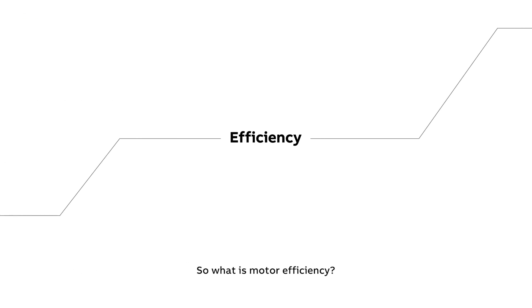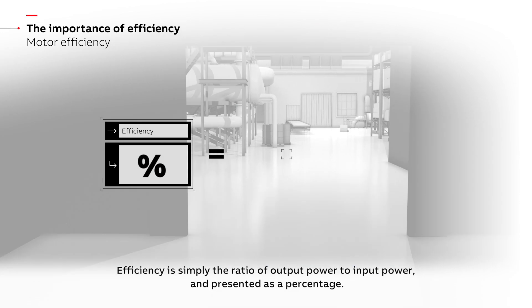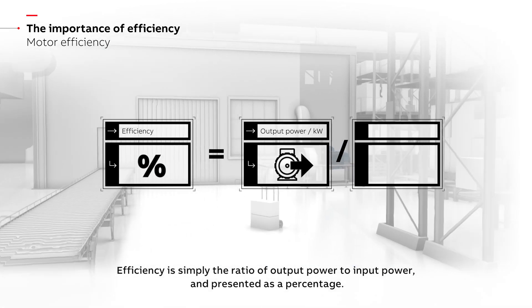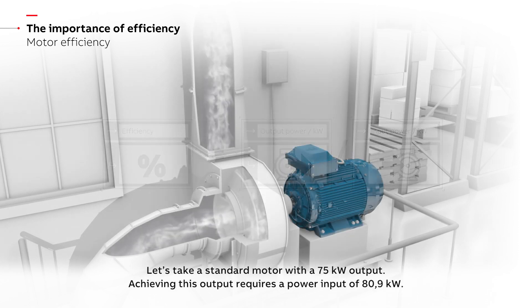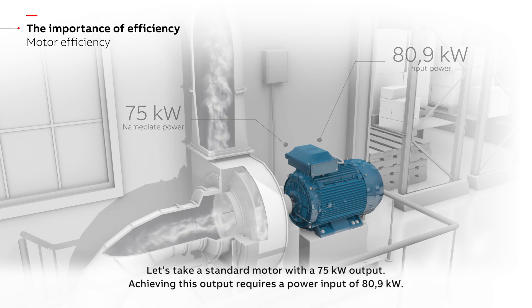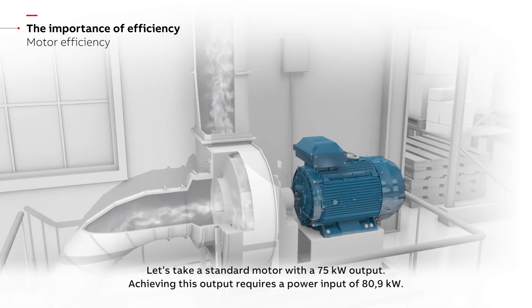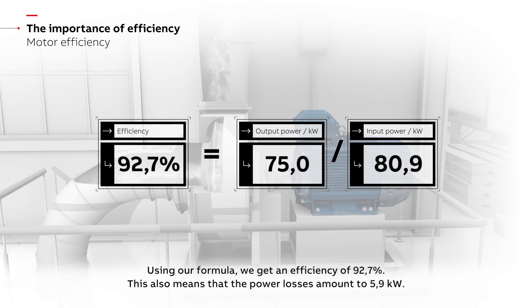So what is motor efficiency? Efficiency is simply the ratio of output power to input power, presented as a percentage. Let's take a standard motor with a 75 kilowatt output. Achieving this output requires a power input of 80.9 kilowatts. Using our formula, we get an efficiency of 92.7%. This also means that the power losses amount to 5.9 kilowatts.